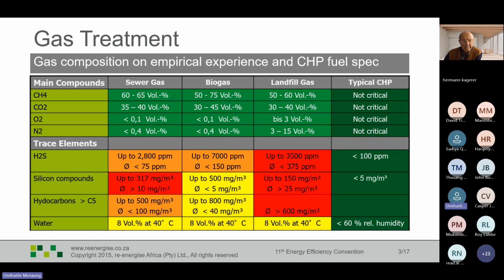You can see the normal biogas we use is much better in terms of trace elements compared to the sewer gas and the landfill gas. For the sewer gas, of importance is the silicon compounds. If you look at the average there of H2S, it's less than 75 ppm, and comparing that with what a typical CHP requires, which is less than 100 ppm, you're looking good there. But if you look at the silicon compounds, the average is greater than 10 milligrams per cubic meter, while the CHP requires less than 5—so that's one element of concern. The rest is okay.